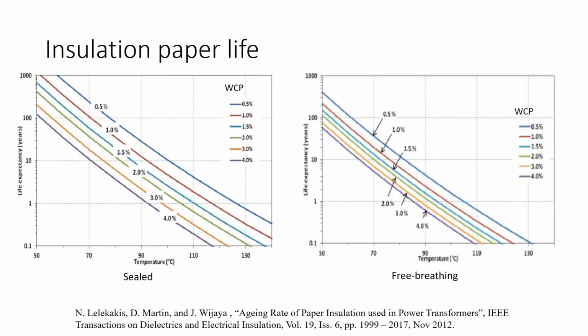Now the temperature is a continuous long-term average. Within a transformer, the load and the ambient temperature are constantly varying. So we would look to convert a continuous temperature measurement into a long-term average weighted temperature. On the right-hand side, we can see that if the transformer is breathing, then the oxygen in the air can have a significant effect. So we shouldn't be running the temperature of a free breathing unit at the same level as a sealed unit if we want to get the same life out of it.